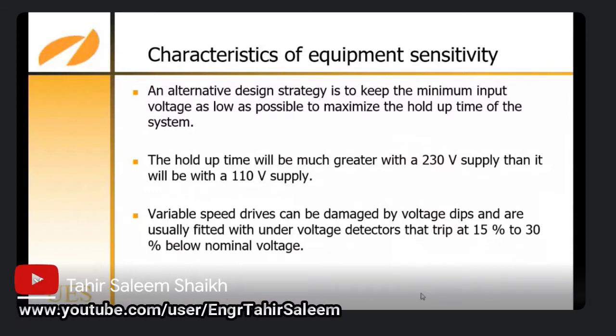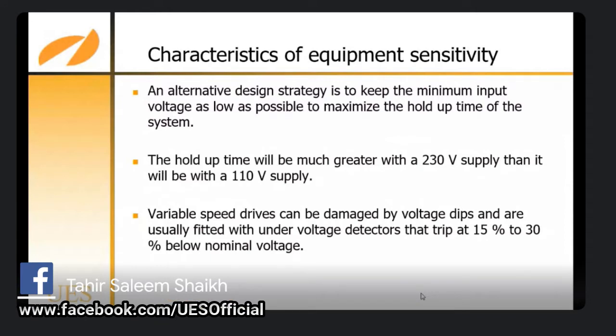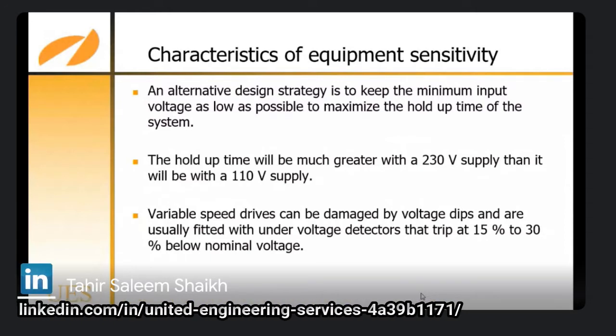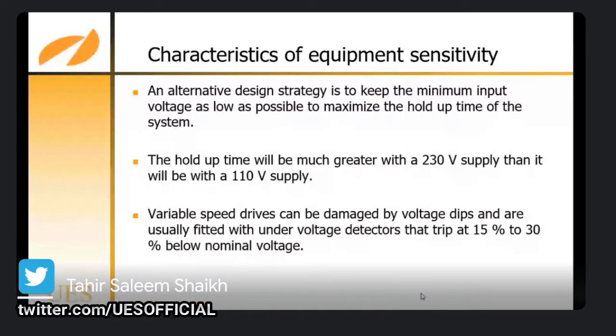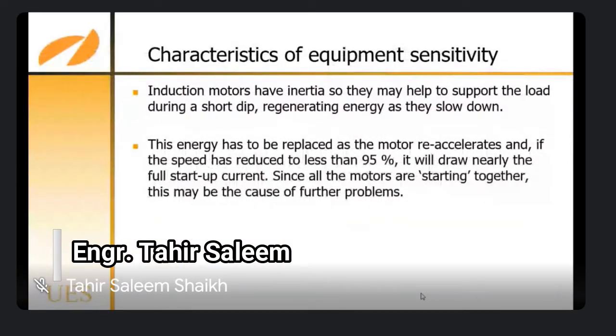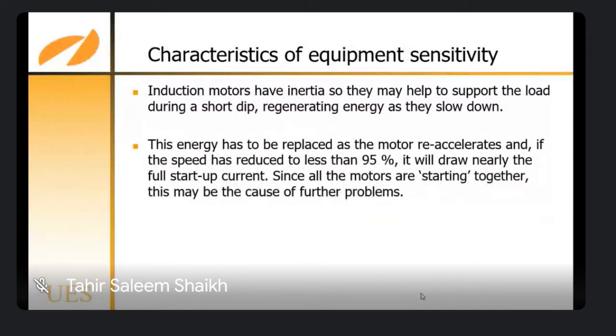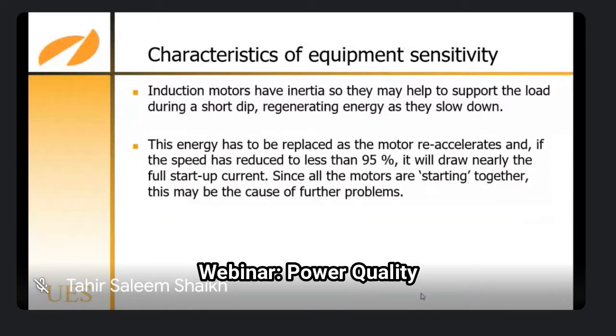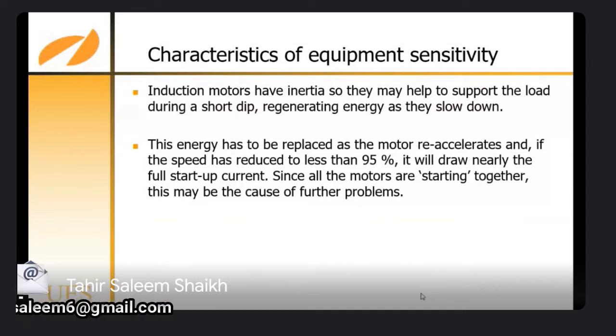Variable speed drives can be damaged by voltage dips and are usually fitted with under voltage detectors that trip at 15 to 30% below nominal voltage. Induction motors have inertia, so they may help to support the load during a short dip, regenerating energy as they slow down. This energy has to be replaced as the motor reaccelerates, and if the speed is reduced to less than 95%, it will draw nearly the full startup current. Since all the motors are starting together, this may be the cause of further problems.